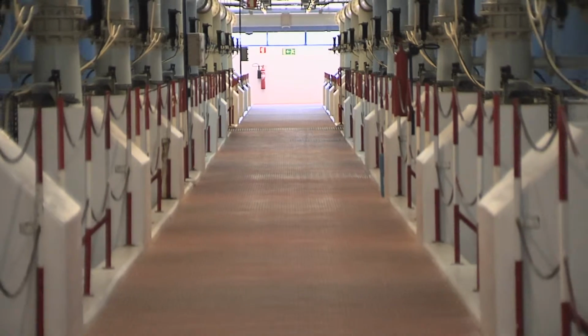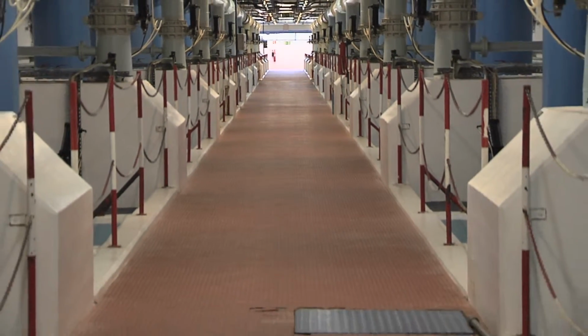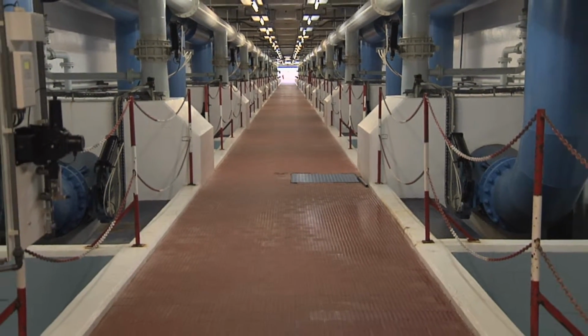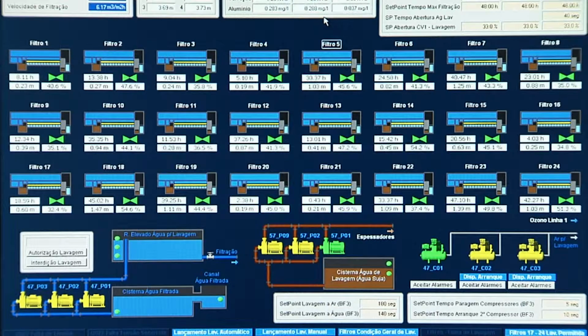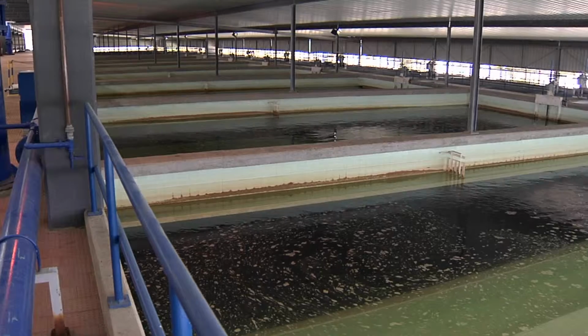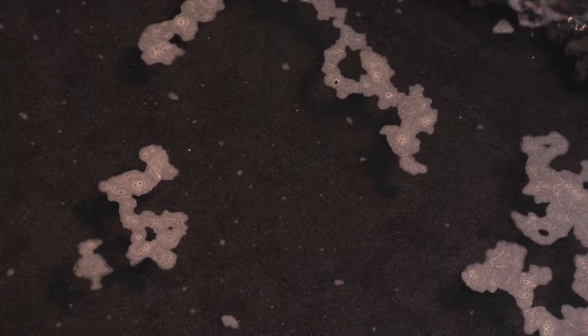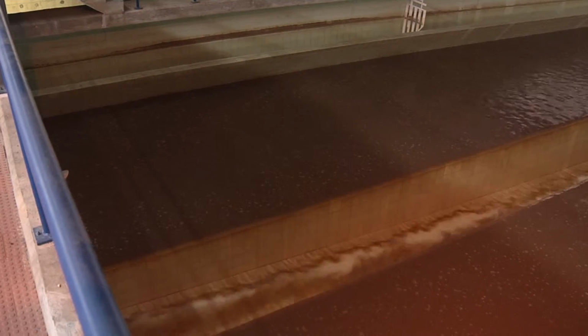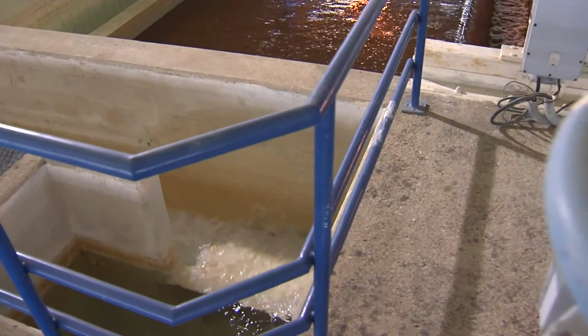The water treatment process consists of 4 phases: physico-chemical treatment, filtration, refining, and disinfection. Unit operations are as follows: pre-chlorination to oxidize suspended material, mineralization and pH correction, chemical coagulation and flocculation, flotation, intermediate ozonation, filtration, pH tuning, post-chlorination for final disinfection, and sludge treatment.